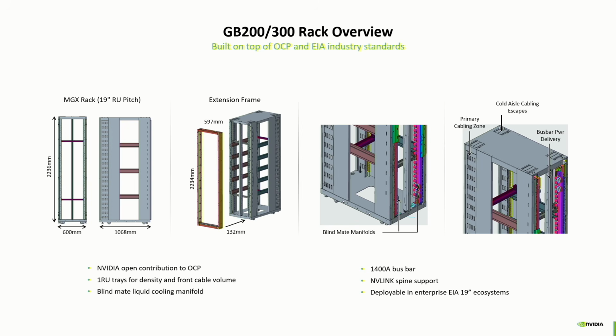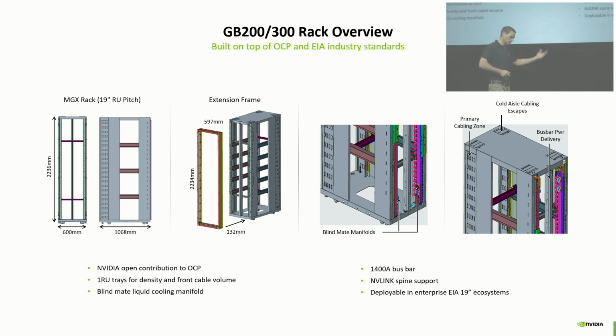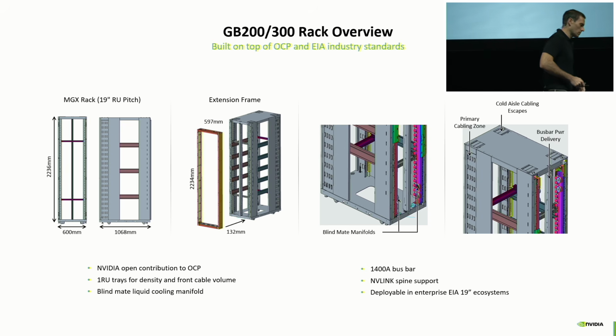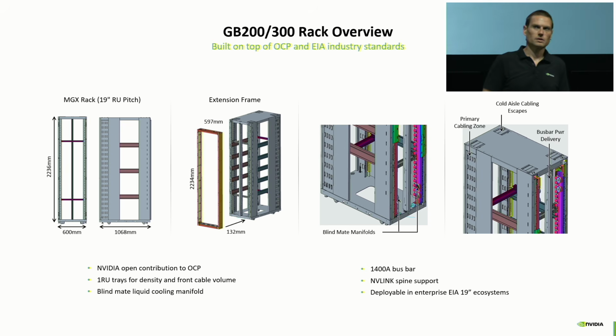I mentioned the bus bar. The bus bar running up and down the back of the rack was capable of approximately 35 kilowatts, and we needed about 4 times that much. So we created a deeper, larger bus bar, with more cross-sectional area of copper, to support up to 1400 amps for this system. That deeper bus bar actually hung out the back of the rack, along with the manifolds and the NVLink spine, which I'll talk about more. So we created an extension frame that wraps around the back of the rack, taking it from a standard 1068 millimeter footprint to the next size up, a 1200 millimeter footprint.